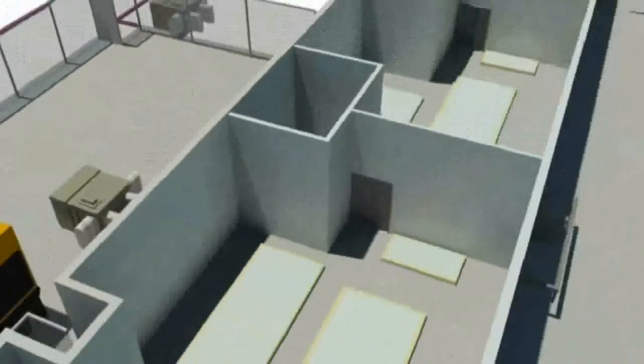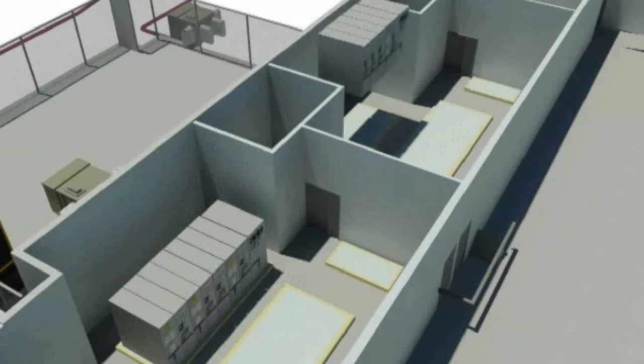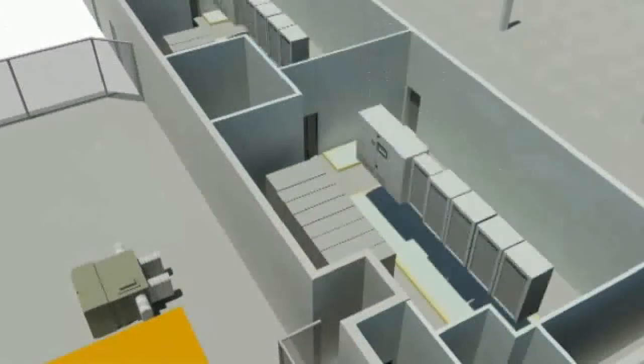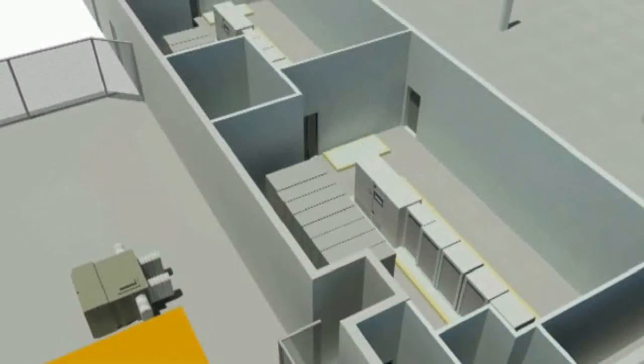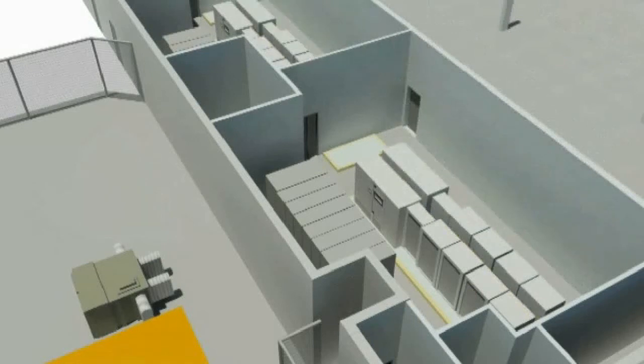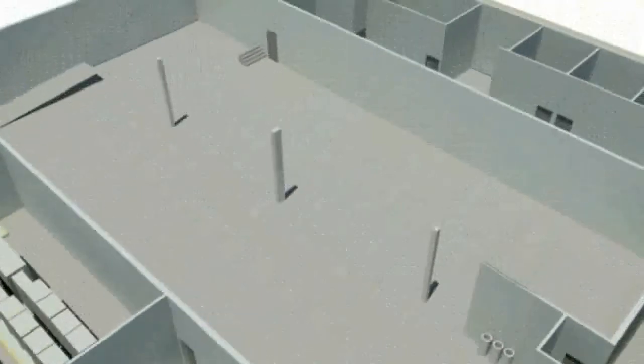All power sources transfer through redundant electrical switchgear, a system that manages a smooth transition of power between supplies as needed. Both the A and B power feeds are also constantly fed into not 1 but 2 uninterrupted power supply rooms that can supply the entire data center as power is being transferred from transformer to generator. There are 2 625 kVA Liebert UPSs. The facility is pre-designed to accommodate a pair of additional UPSs. It is just one more way we ensure that power to the customer equipment is never absent, regardless of any emergency or unexpected power failure outside the facility.